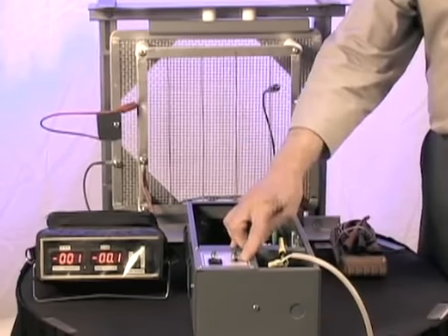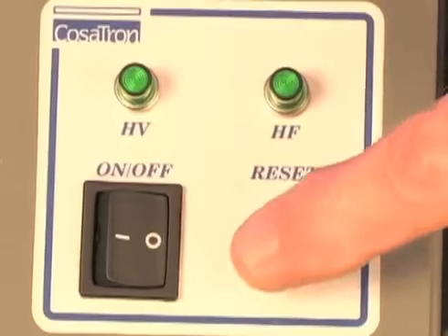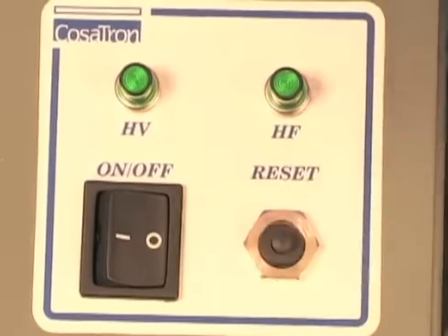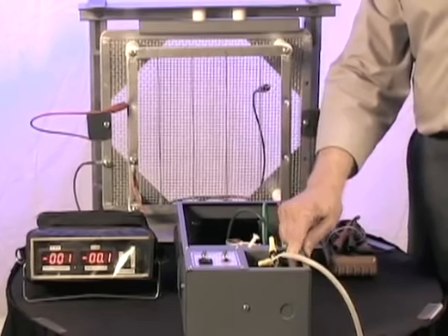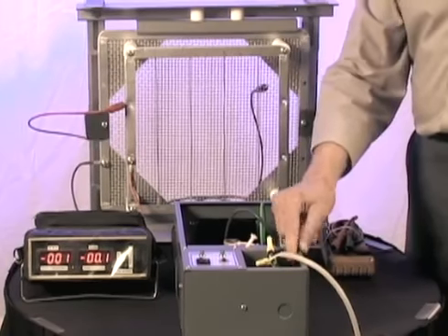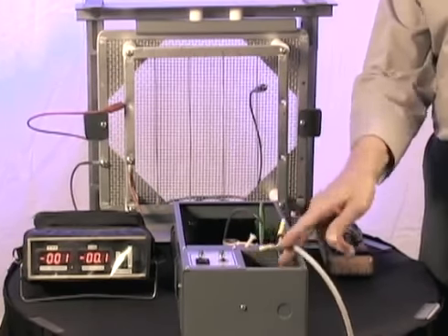Or if your circuit breaker has been actuated, punch the post back in. This will or should reset the circuit breaker and restore incoming power. If it does not, you probably have problems with your incoming power.